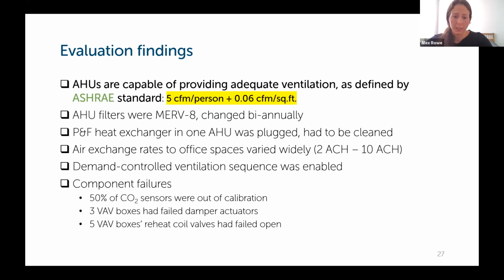The controls contractor noted that the demand controlled ventilation sequence was enabled. So that means that outside air dampers were at their minimum position because the building was unoccupied, and VFDs were running at minimum speed unless there was a call for heating and cooling. So they weren't maximizing the airflow that the system was capable of.